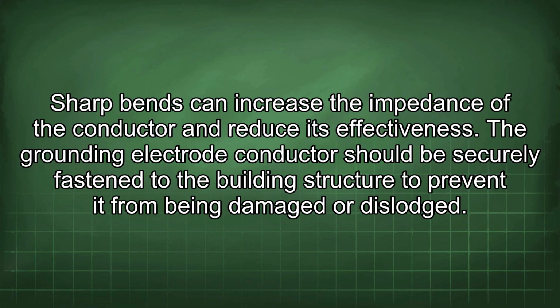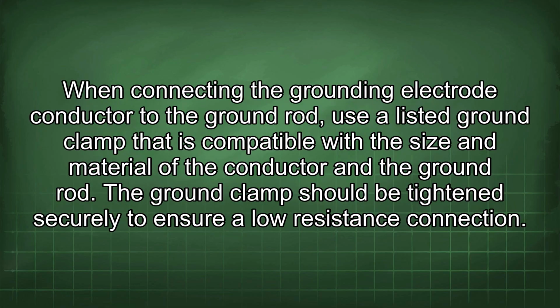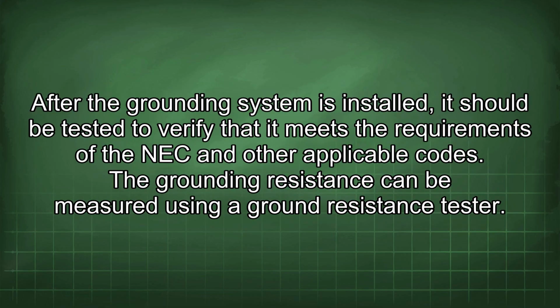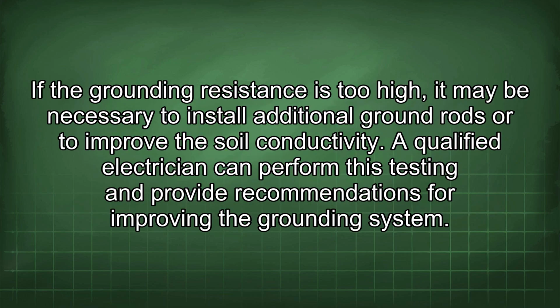The grounding electrode conductor should be securely fastened to the building structure to prevent it from being damaged or dislodged. When connecting the grounding electrode conductor to the ground rod, use a listed ground clamp that is compatible with the size and material of the conductor and the ground rod. The ground clamp should be tightened securely to ensure a low resistance connection. After the grounding system is installed, it should be tested to verify that it meets the requirements of the NEC and other applicable codes. The grounding resistance can be measured using a ground resistance tester. If the grounding resistance is too high, it may be necessary to install additional ground rods or to improve the soil conductivity. A qualified electrician can perform this testing and provide recommendations for improving the grounding system.